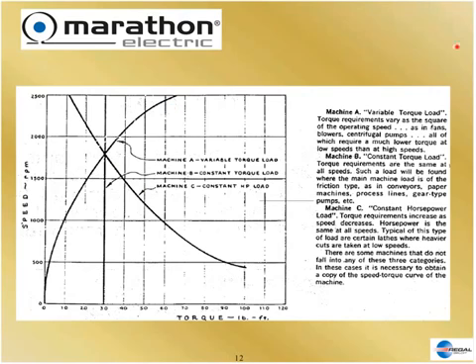A typical application of a variable torque load is a blower or fan. If you turn the fan blades when the fan is off, you can turn them very easily with one finger. But as the motor turns the fan up to speed and air starts to blow, now you have power. Machine B is a constant torque load — the constant torque load is not speed-dependent; it doesn't change with speed because the load is always impressed on the shaft at the same value. A typical example would be a conveyor: if you put 100 pounds on a conveyor, the motor has to move 100 pounds regardless of speed.